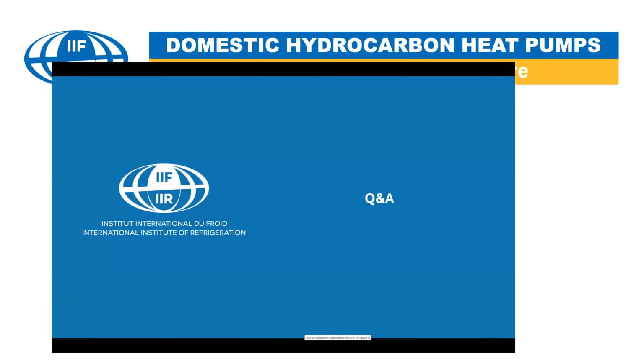One of the presentations mentioned there is no clear evidence of the relationship between the refrigerant charge and the COP, or the performance of the system. I wanted to find out, is this the case for propane applied in heat pumps, or what is the case? According to research I've done, I've seen the performance of the system, maybe using R134A, influenced by the quantity of refrigerant charge into the system. Could you please give some clarity on that?